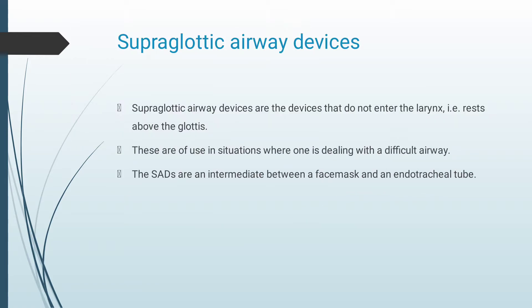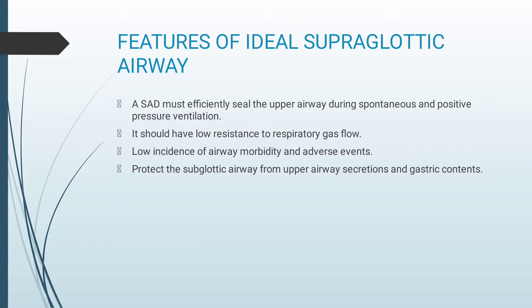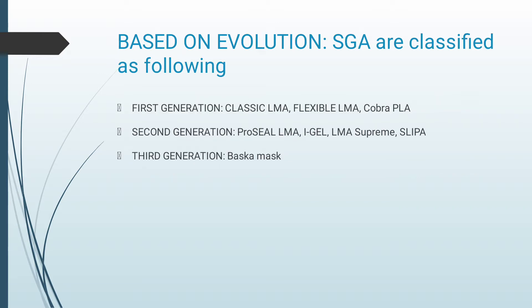Moving on to supraglottic airway devices. Supraglottic airway devices are devices that do not enter the larynx — that is, they rest above the glottis. These are of use in situations where one is dealing with a difficult airway. Supraglottic airway devices are an intermediate between a face mask and an endotracheal tube. A supraglottic airway device must efficiently seal the upper airway during spontaneous and positive pressure ventilation, have low resistance to respiratory gas flow, and a low incidence of airway morbidity. Based on evolution, these have been classified as 1st, 2nd, and 3rd generation.